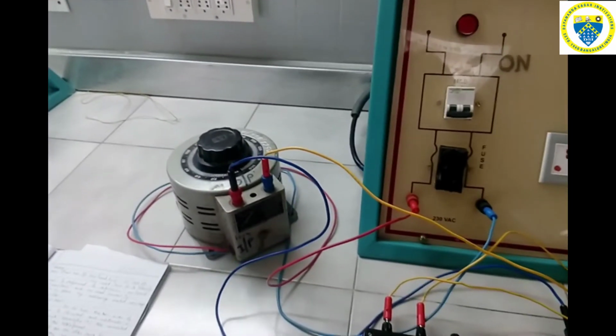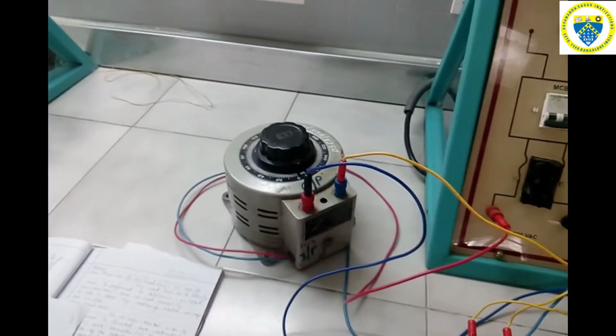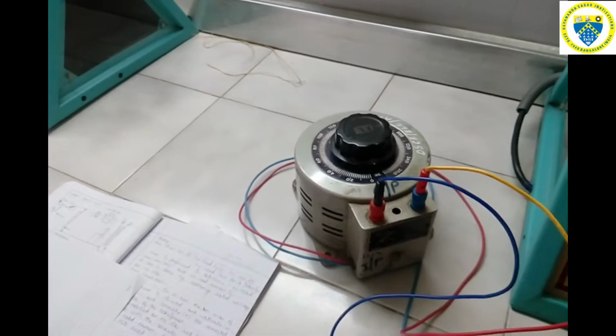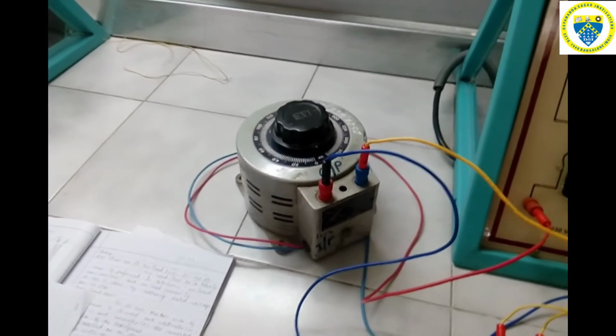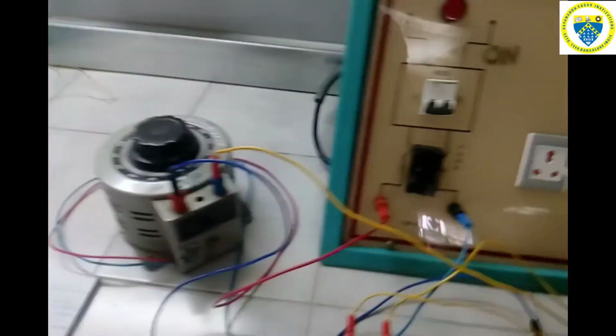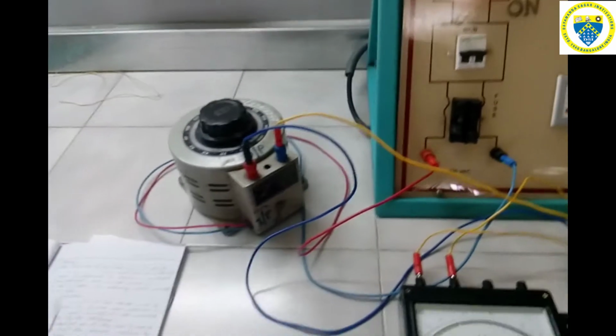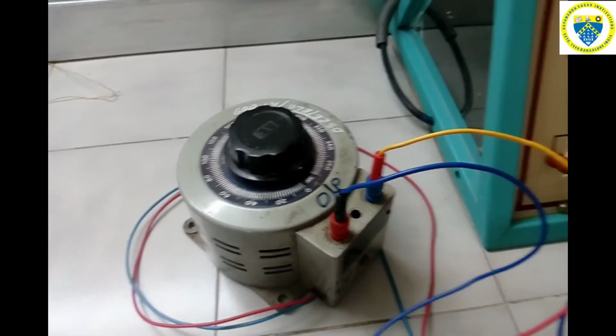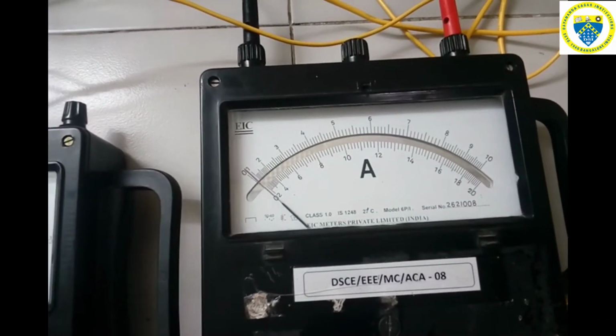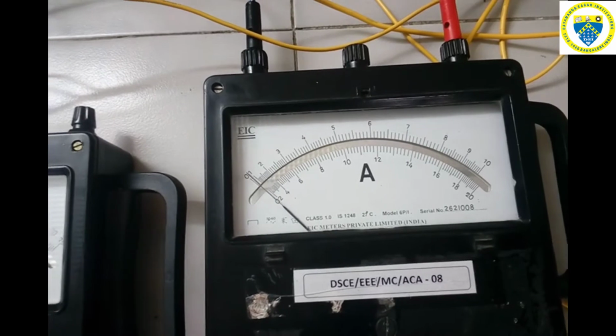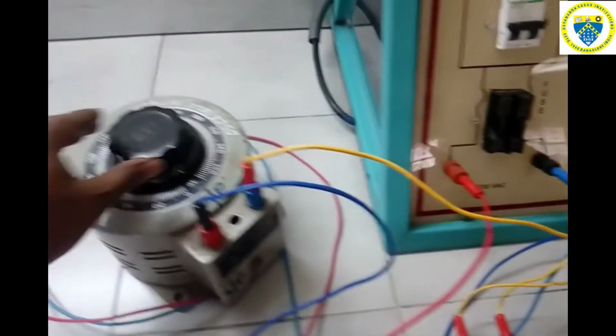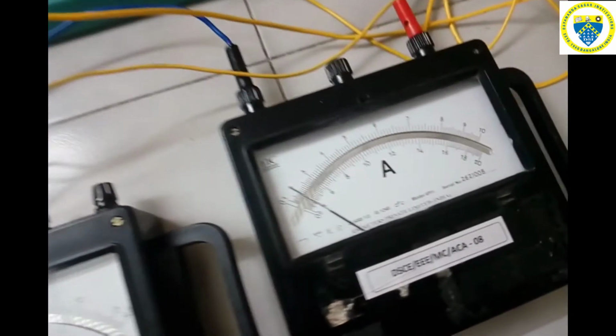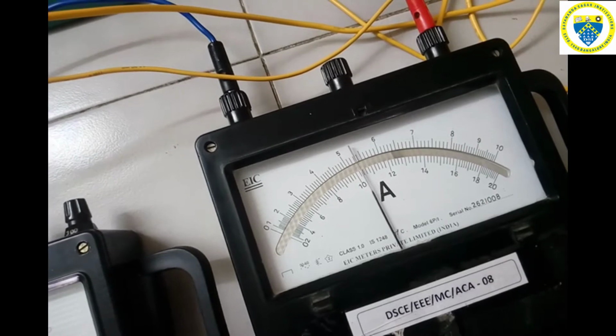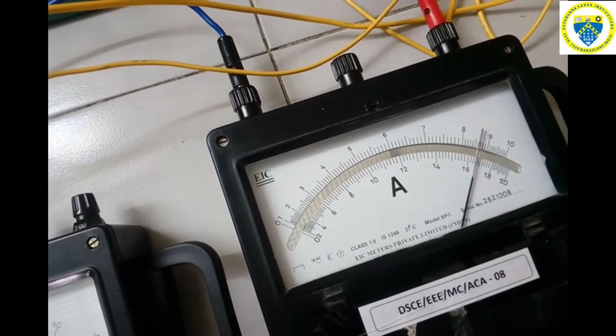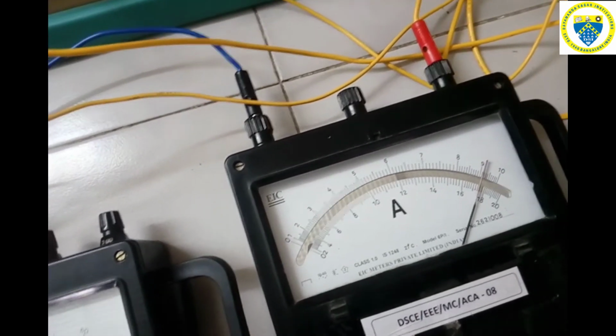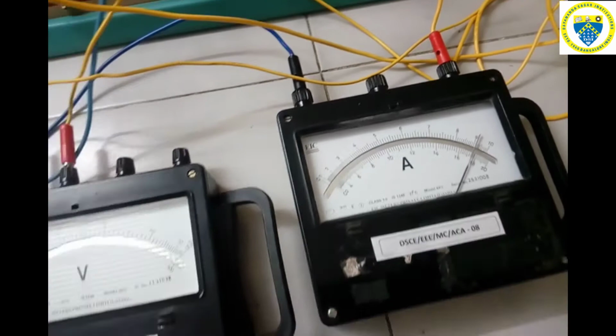Before doing this experiment we should take the precaution of checking the zero position of the auto transformer. If it is not at zero, we should bring the auto transformer to the zero position. After confirming it, we should switch on the main supply. Then gradually by varying the auto transformer slowly, we should check the ammeter so that it reads the rated current of 9.09, that is around 9.1 amperes.